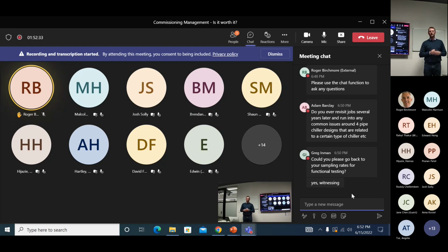No, that's not true. So I often say, let's witness everything - it won't take long since you've got to go through it anyway, I'll just walk behind you. I find that something like 1 to 2% of the installed detectors aren't working. If you're in the office and it's one of those not working during a fire, you'll be pretty upset. So I find that's worth doing. I also like to test all the interfaces, because as I mentioned earlier, that's where it all goes wrong.